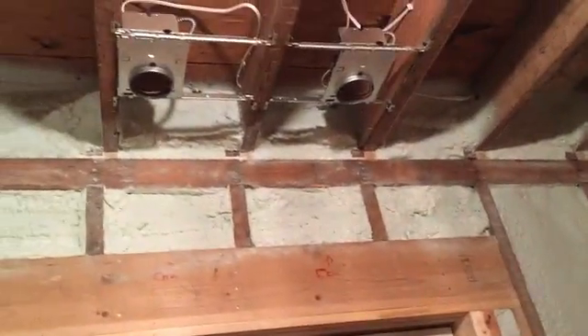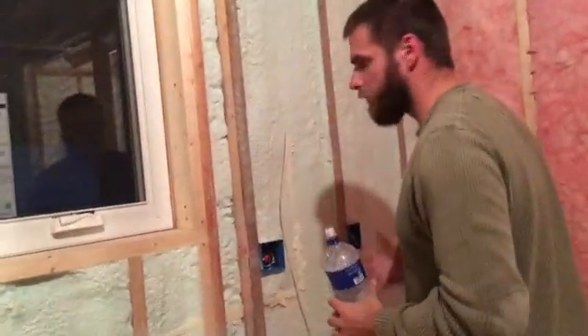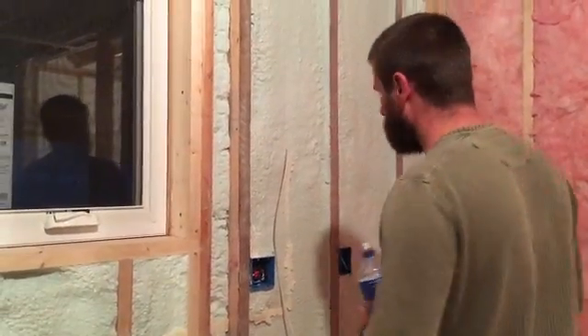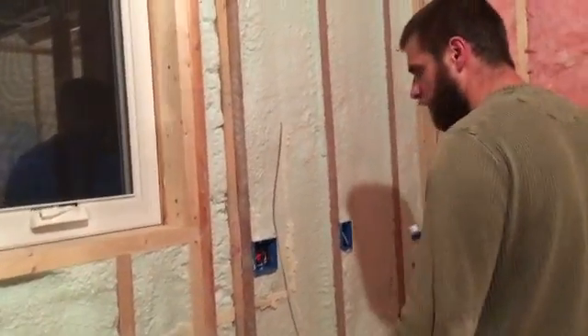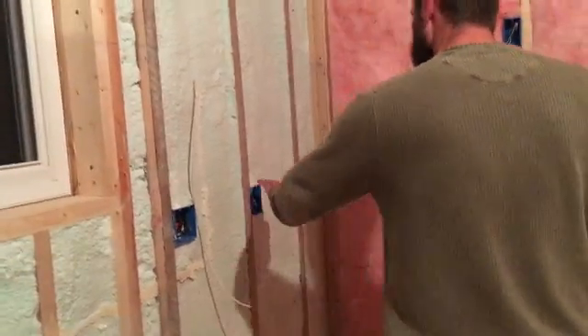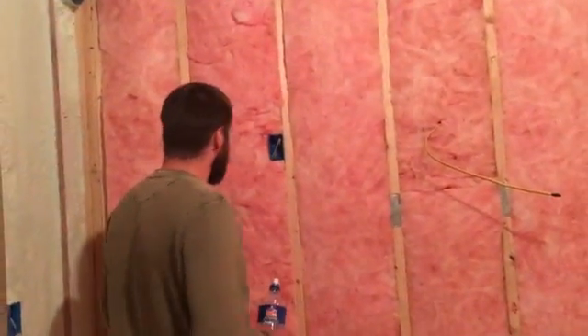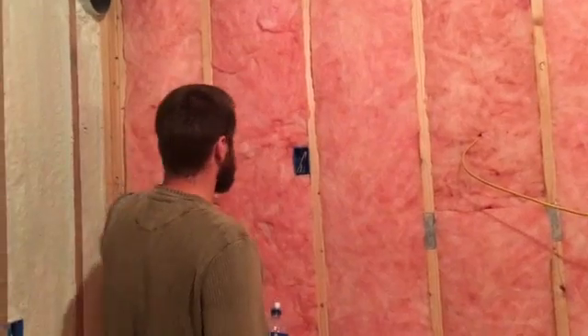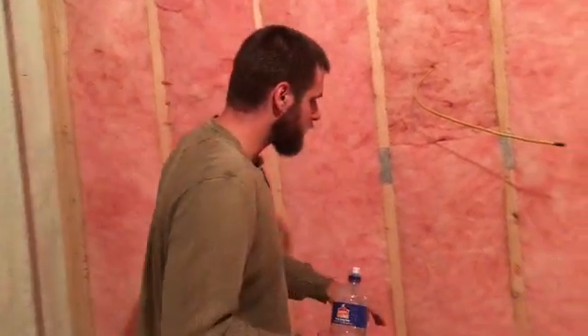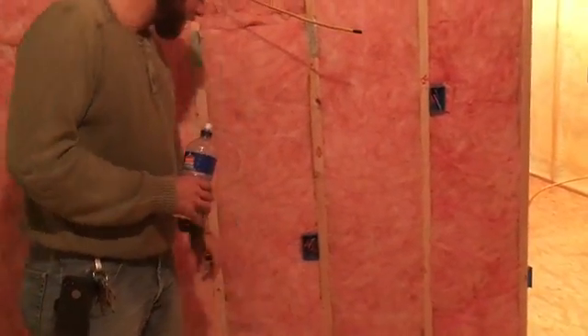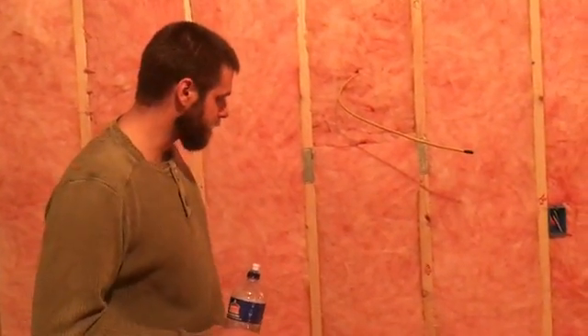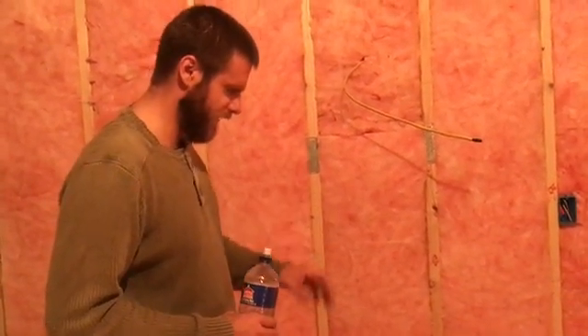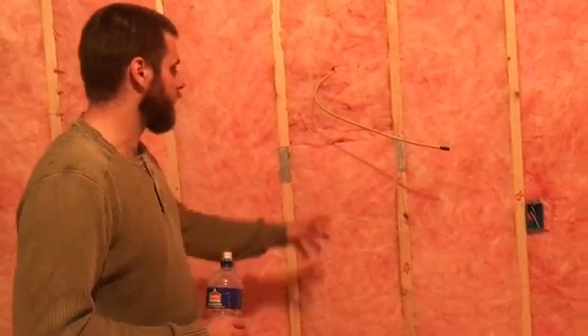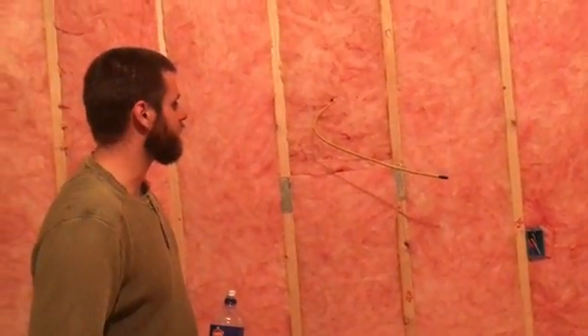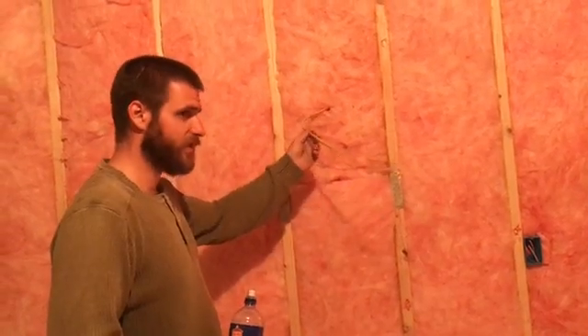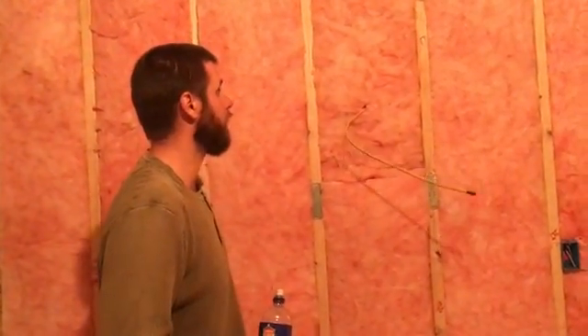I opted to put two lights in, and we'll have a dimmer on them so we don't have to run them really bright, but I don't think you can have enough light when you're cleaning things. Then a secondary switch for if we ever want to add a garbage disposal. These are just countertop height outlets. This will be a box for a microwave, so this will be an outlet, and this is a utility outlet for the range. If you have a gas range it'll have igniters that need electricity, as well as if you have a clock or anything like that - they need a 110 service. This little wire sticking out here will be for our range hood.